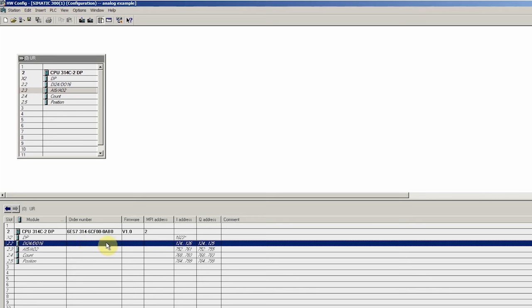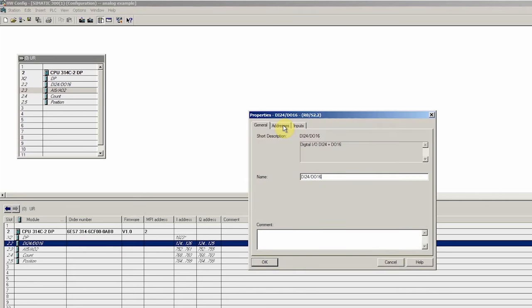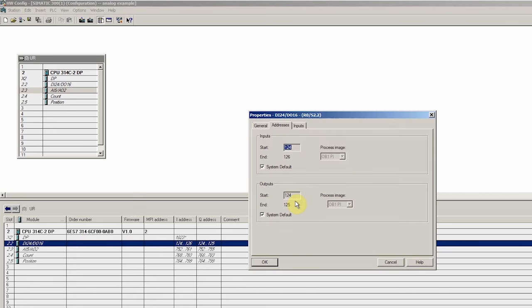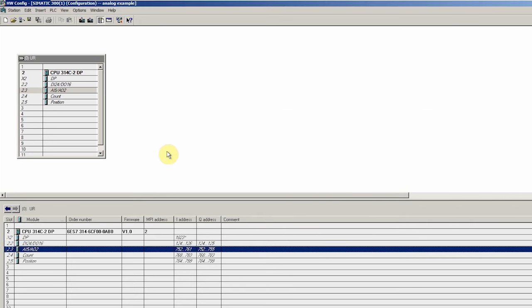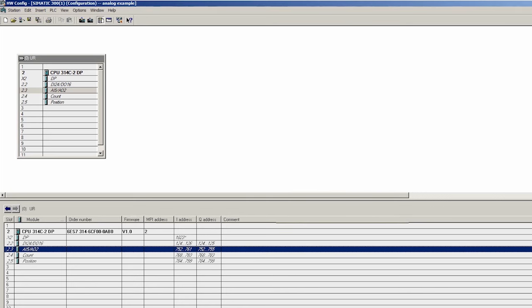Now if we click on the address tab, we can see that the address for channel 0 is 752. Next, if we open the properties of the digital signals, we can see that the address of the digital outputs is starting from 124. This means the address of the first digital output is Q124.0. Q124.0 digital output will be turning on and off the relay for the VFD run command. Next we will save and compile the hardware configuration and open programming block OB1.